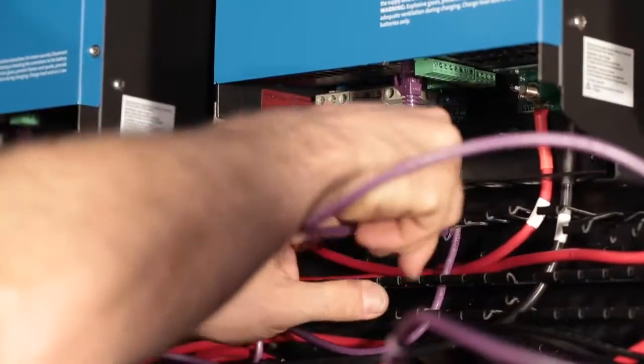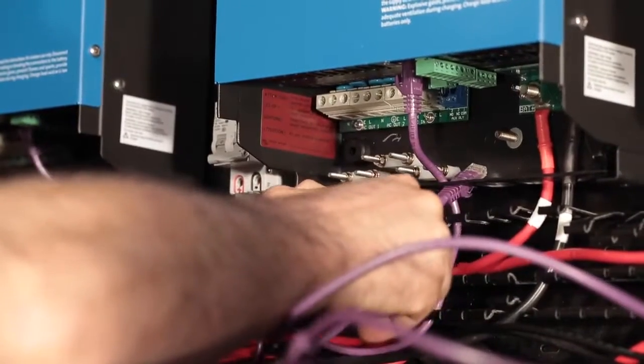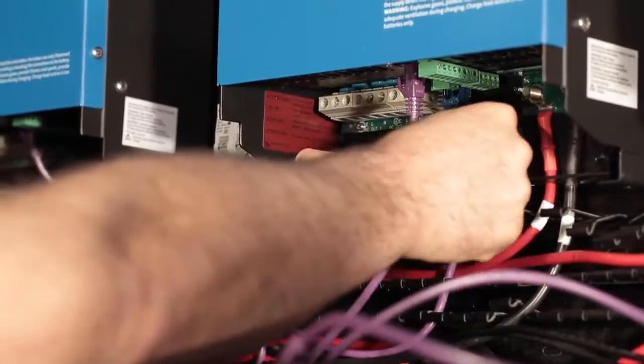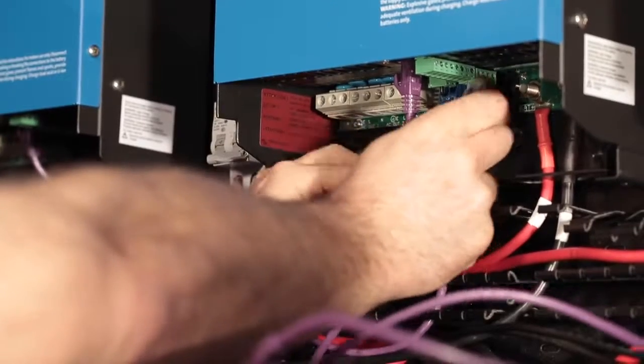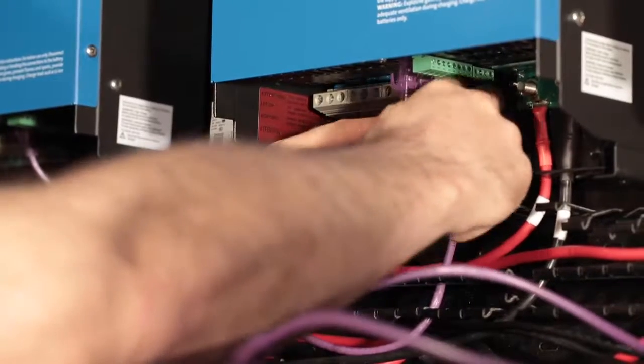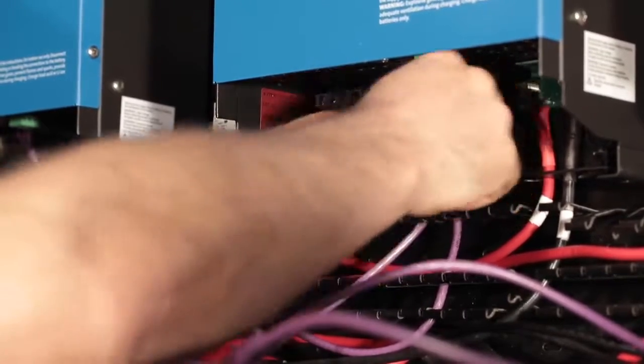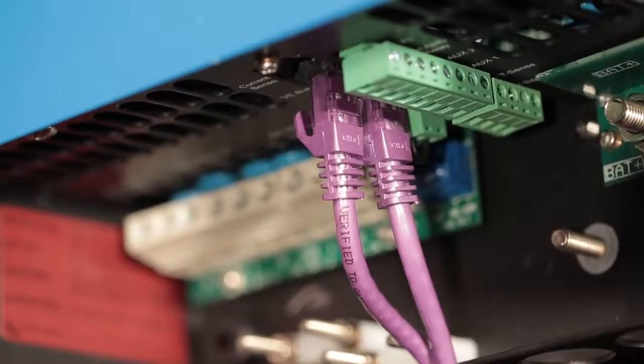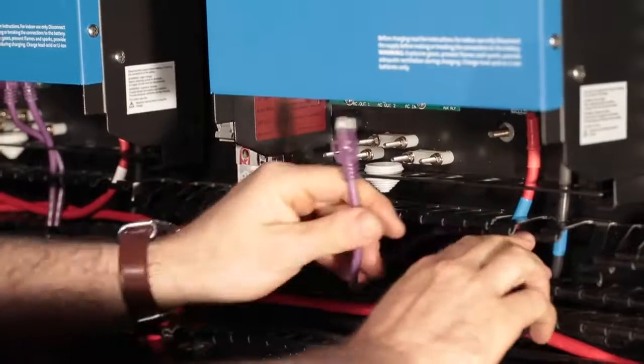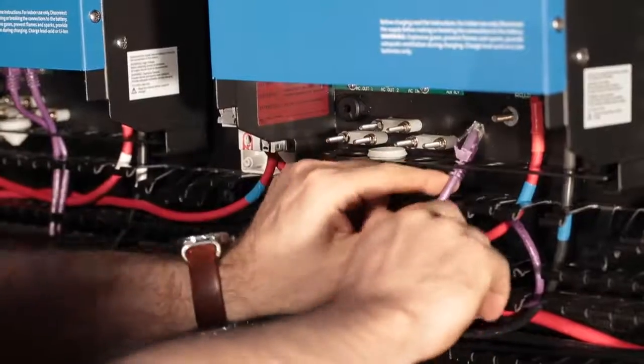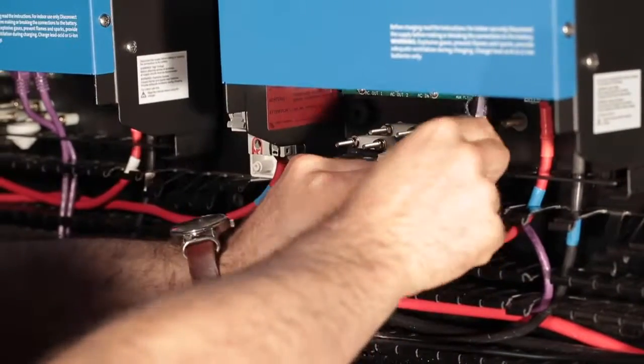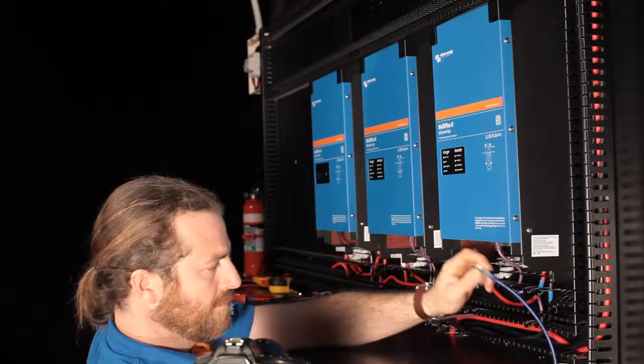Each unit is daisy chained into the other. Please consult the wiring diagram for exactly how this is done. The exact location of the VE.Bus port will vary depending on the unit you've got. Here you can see it's located on the bottom. Once the units are all connected together like this, they won't function properly until they're properly programmed.